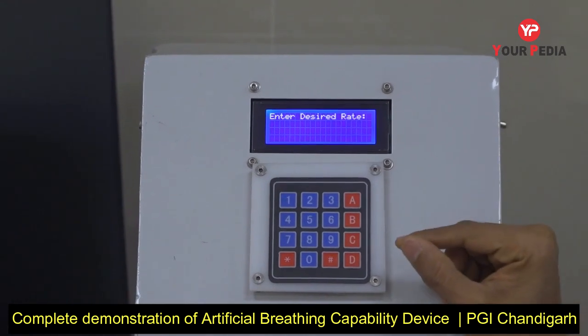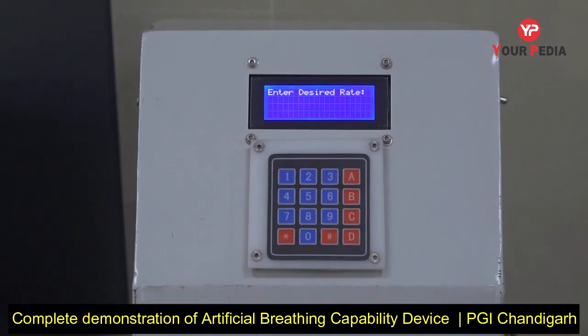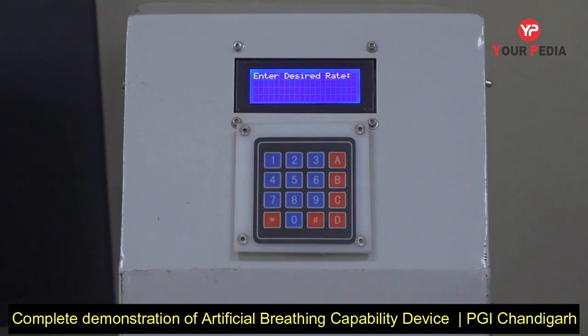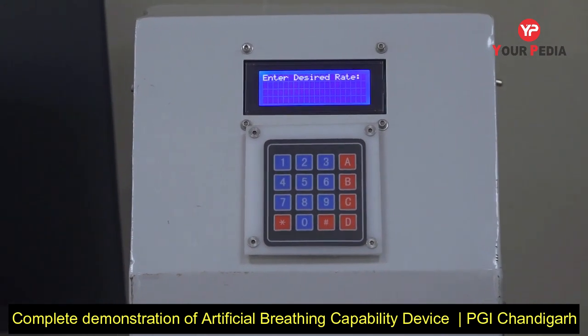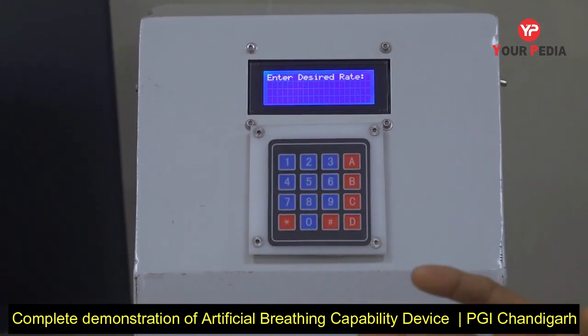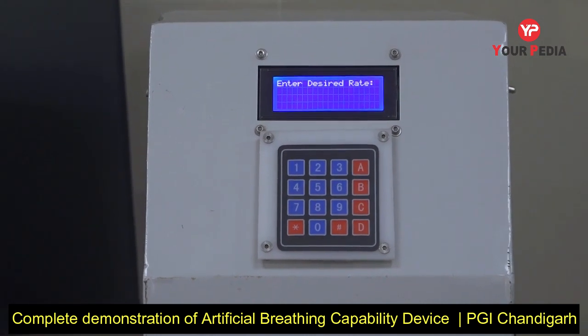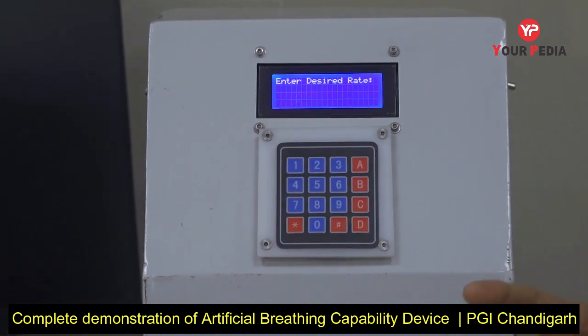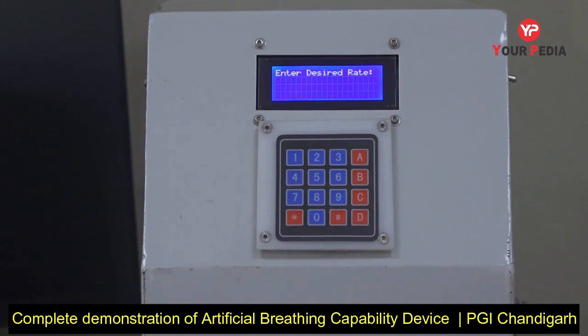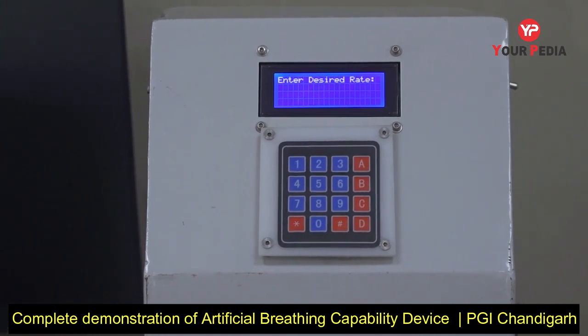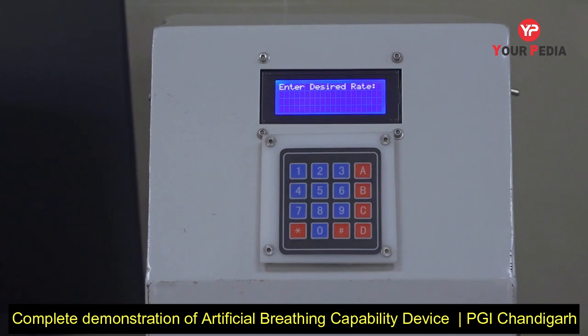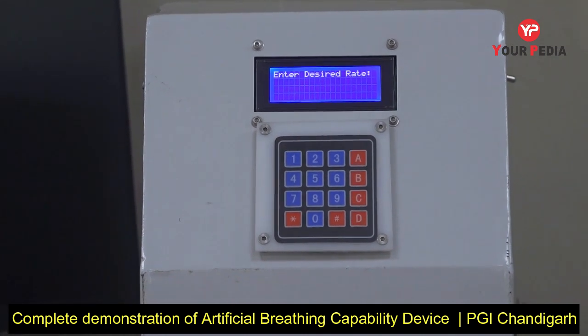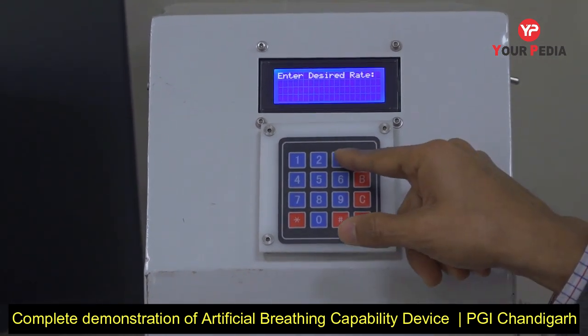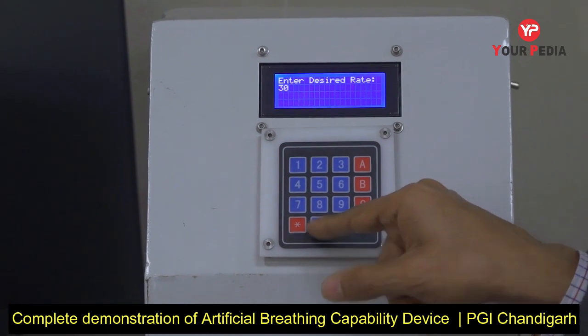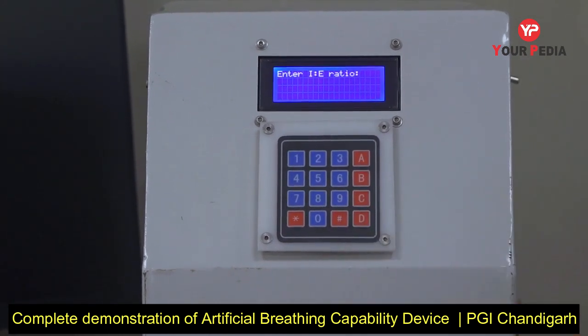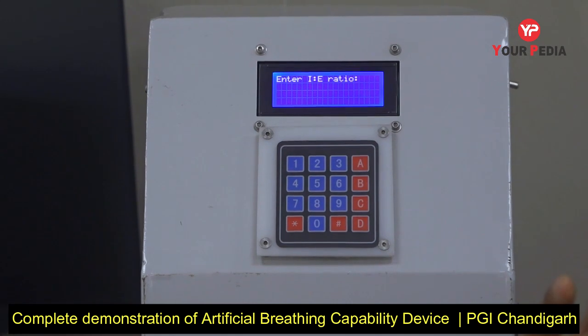Immediately the ventilator asks me to set a desired rate. This device can ventilate at a rate as low as 10 per minute to as much as 60 per minute. Most other devices of this kind are not able to go beyond 30 per minute. But this device has a very fast motor with which we are able to ventilate up to 60 per minute, which is required sometimes in the pediatric age group and also in newborn infants. So let us set a respiratory rate of 30 per minute. This means each cycle would be 2 seconds in duration.